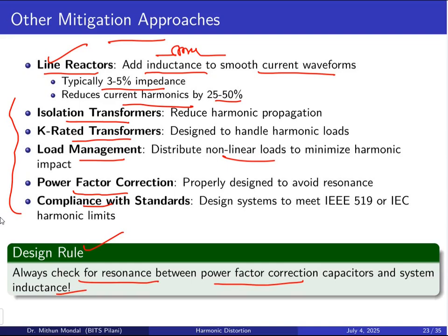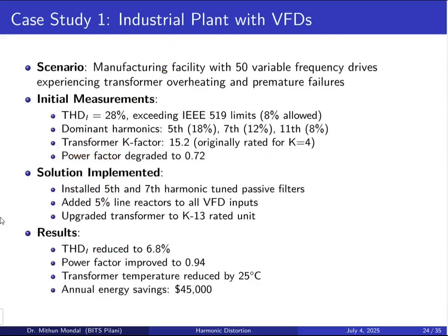So resonance plays a very important role in harmonics. So we have to check this harmonics, what are the order of the resonance present in the capacitor and the system inductance. We'll take certain case studies. Case study 1, where we talk about the industrial plant using the variable frequency drives.